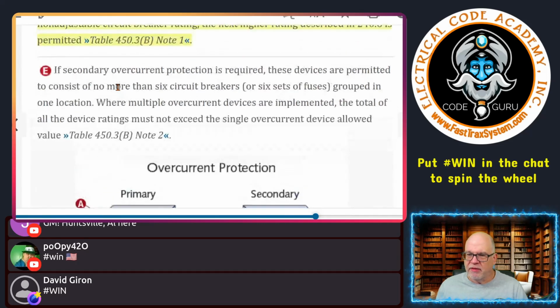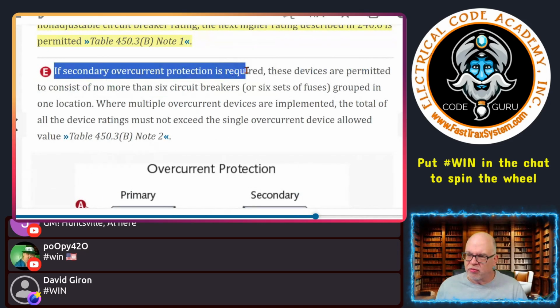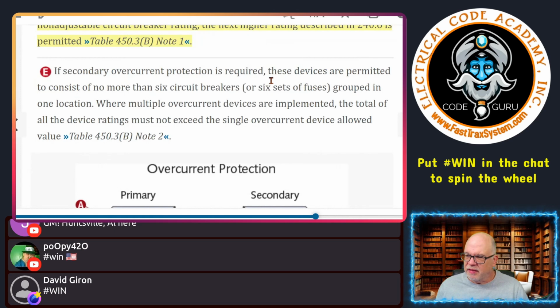Now, it says if secondary overcurrent protection is required, these devices are permitted to consist of not more than 6 circuit breakers or 6 sets of fuses grouped in one location. Now, y'all remember for services, we got rid of that, so you can't have the 6 throws, but it is still acceptable for feeder applications, and it most certainly is still acceptable for the secondary application. So you could feed from the secondary of a transformer into main lugs, and then you have 6 separate circuit breakers in there.